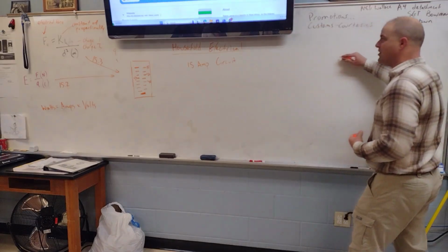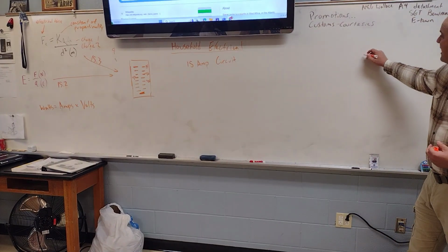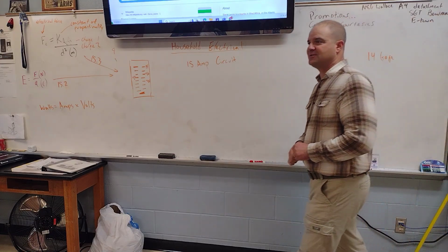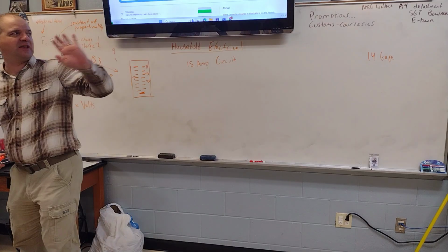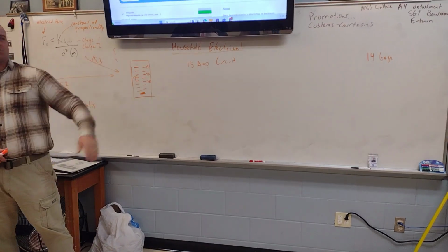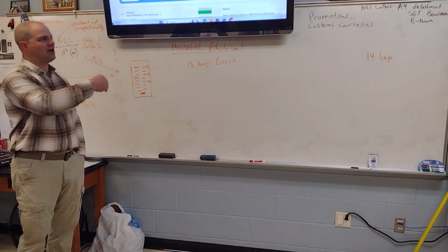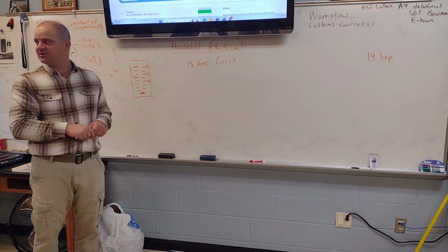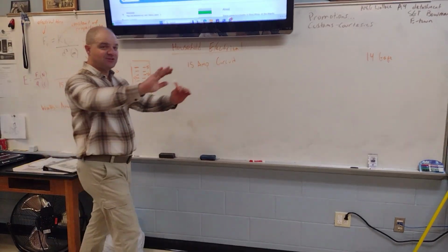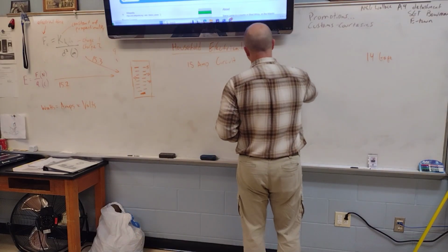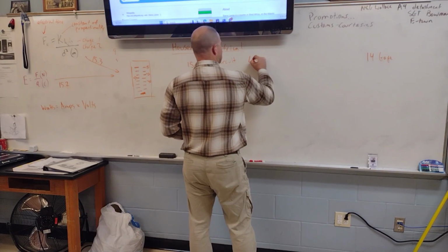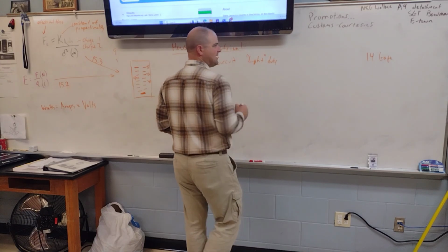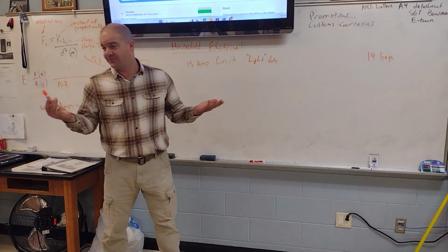I'm going to come way over here on the same line, and it uses 14 gauge copper wire as the conductor. Okay, put that in your notes all the way on the end. You can wait if you want to, because I'm going to put stuff in between there. So a 15 amp circuit uses 14 gauge wire, which is fairly thin, kind of nice and flexible, easy to use. It's used for things like lighting. So a 15 amp circuit is light duty. And I'm going to put quotes around light because often they're used for lighting.